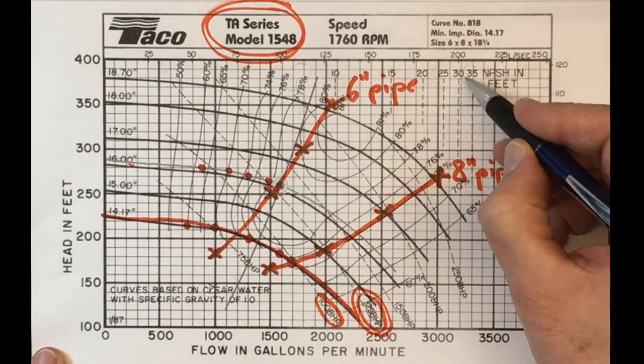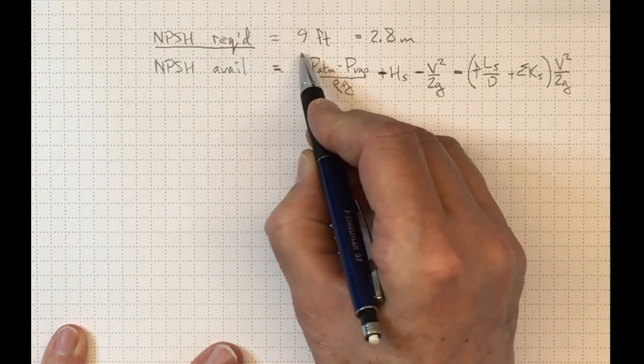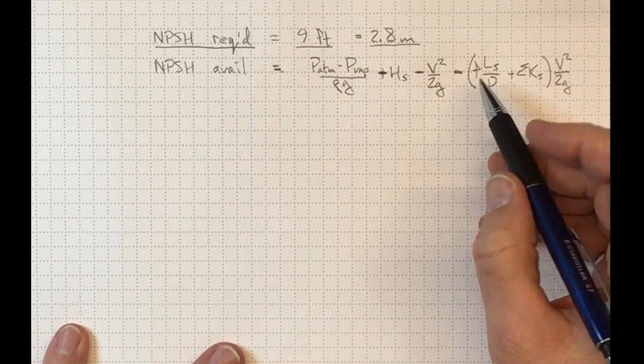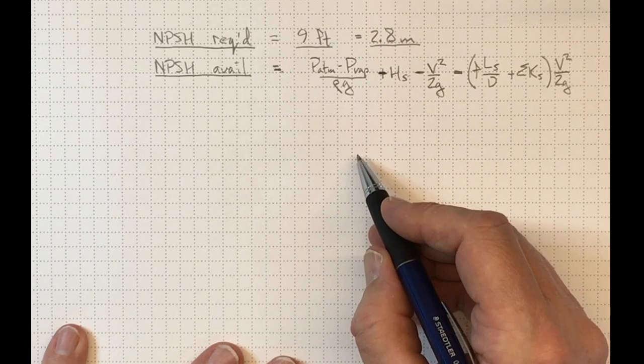So a fairly low requirement to avoid cavitation. It could go much higher, say around 35, if we're going to really high flow rates and velocities. So if our NPSH required is 9 feet, or 2.8 meters of head, then we can calculate the NPSH available and see if we make it.